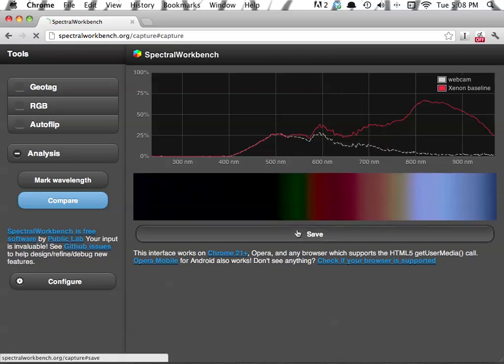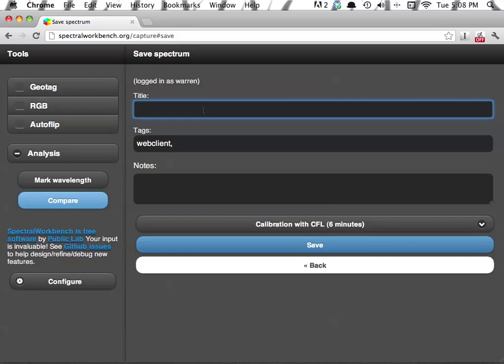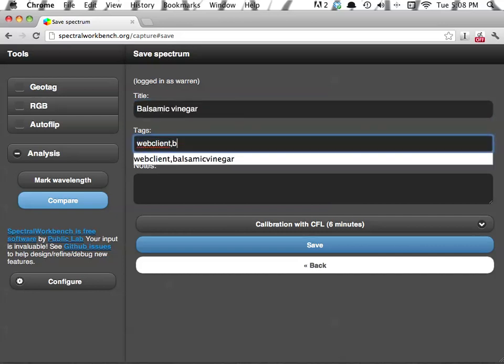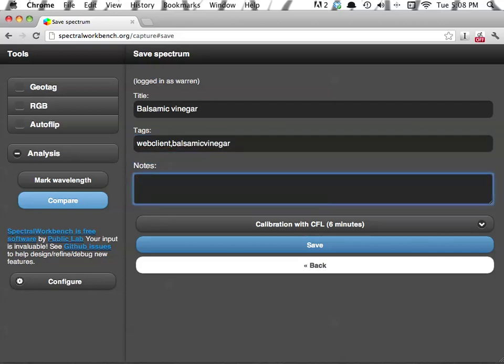If you want, you can hit save and type in balsamic vinegar, because I've done this one before. And then you might say back lit with xenon. You can see it's got a calibration that it did 6 minutes ago, and it auto-associates that as the most recent one. You can calibrate as often as you like.